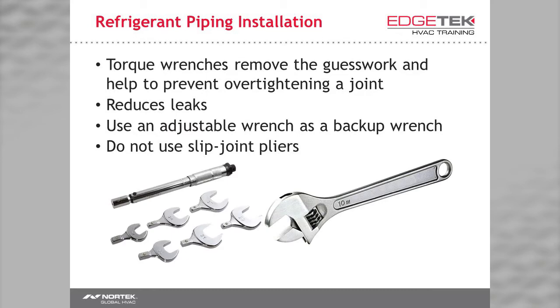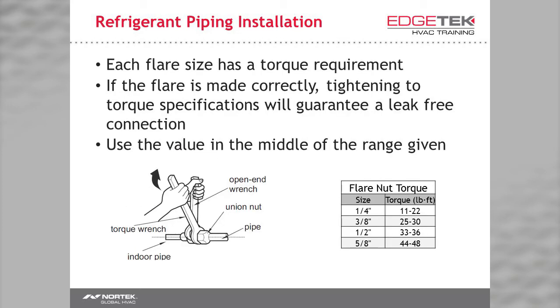Now that we can make a proper flare, we need to tighten it correctly. The only way to know how tight it is is to use torque wrenches. This also prevents over-tightening and the thinning of a flare. Every installation manual has a chart showing you the amount of pounds-feet or Newton meters for tightening. Select a value within these ranges for the corresponding size and set your torque wrench accordingly.